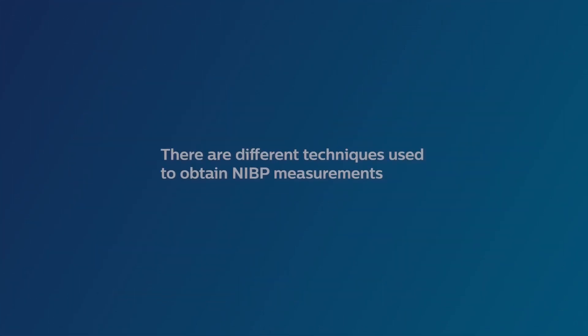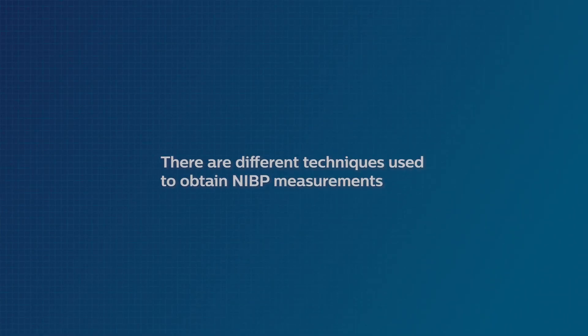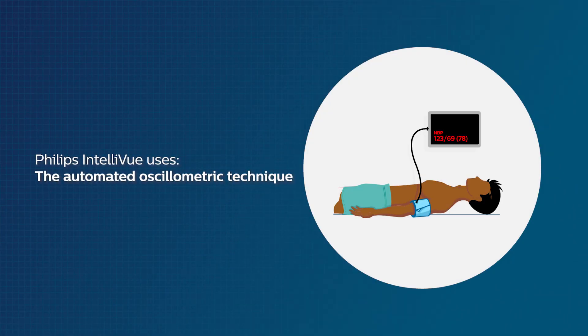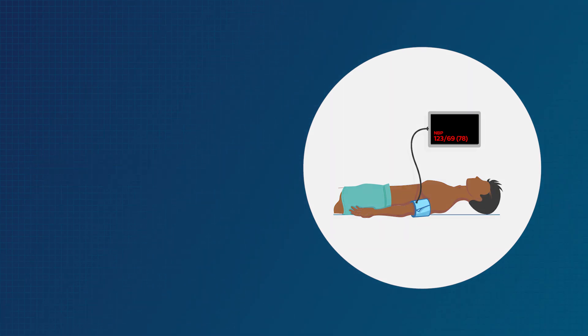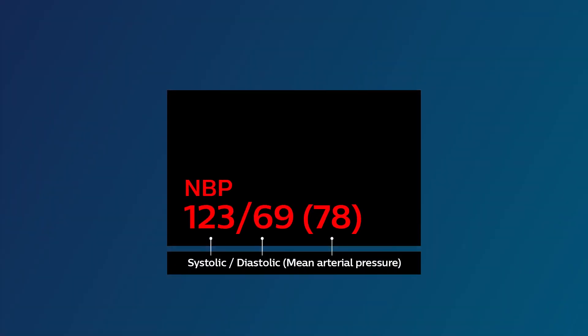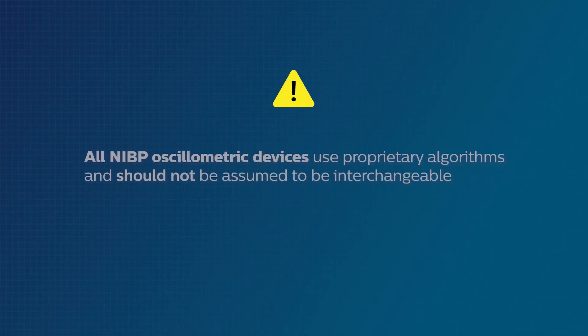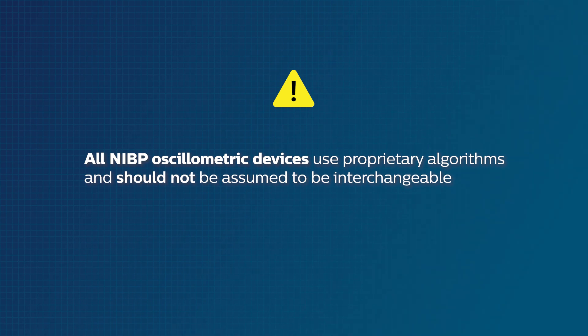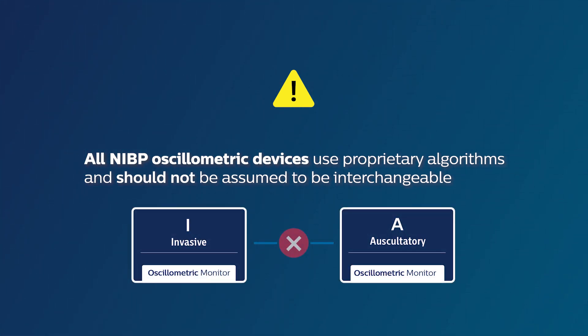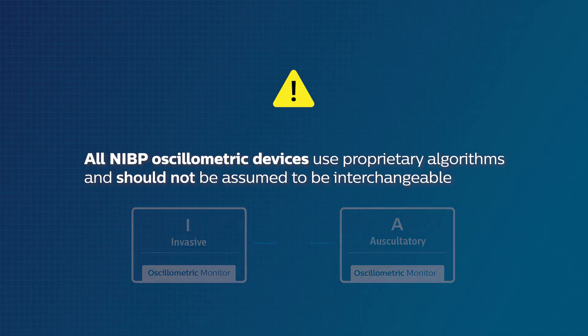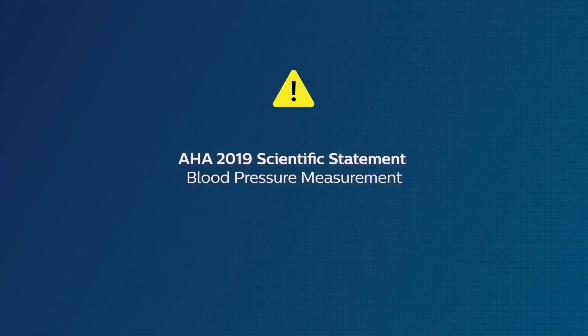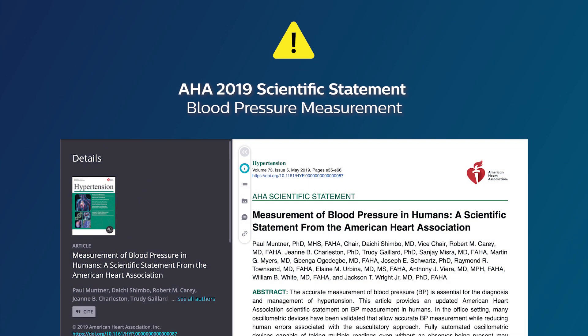Different techniques are used to obtain NIBP measurements. The Philips IntelliVue patient monitors use the automated oscillometric technique to determine the systolic, diastolic, and mean arterial pressures. It's important to note that all NIBP oscillometric devices use proprietary algorithms and should not be assumed to be interchangeable. Only those that have been independently validated with an established protocol should be used, as described in the AHA 2019 Scientific Statement on Blood Pressure Measurement.